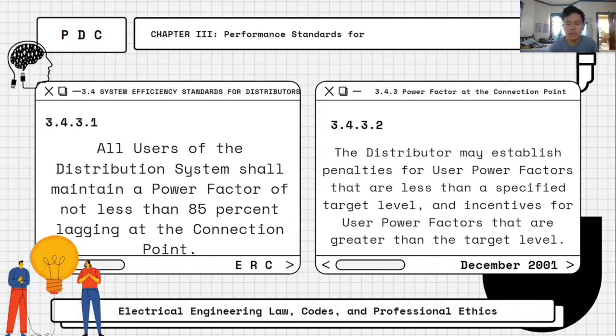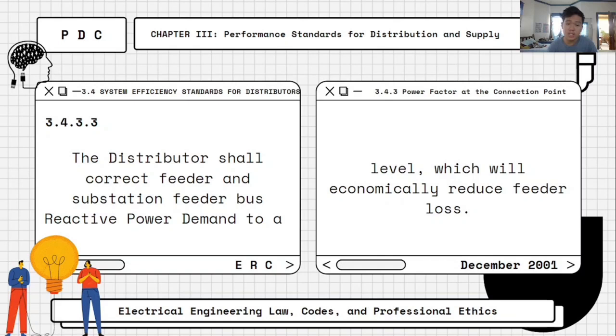Under Chapter 3.4.3, power factor at the connection point: power factor measures how efficiently electrical power is converted into useful work output. All users of the distribution system shall maintain a power factor of not less than 85% lagging at the connection point. The distributor may establish penalties for user power factor below a specified target level and incentives for power factor above that target. The distributor shall also correct feeder and substation feeder bus reactive power demand to a level which will economically reduce feeder loss.